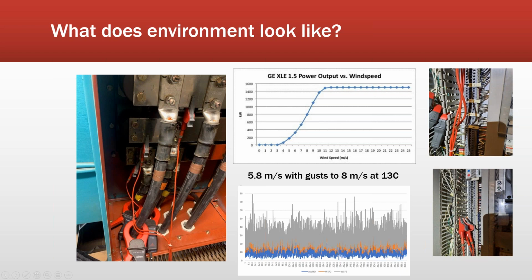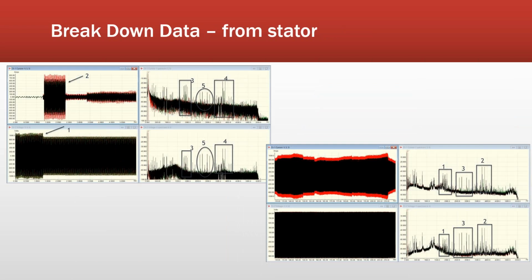then for most of them, we actually took the data in the base of the tower, so we didn't have to shut it down, and we didn't have to have people climb twice on a tower. Very rarely do we do that. And for your GEs and Suzlons and several others, you don't need to. It's all taken down tower. Siemens and a few others, you do have to go up. So let's take a closer look. Here are the transformer readings.